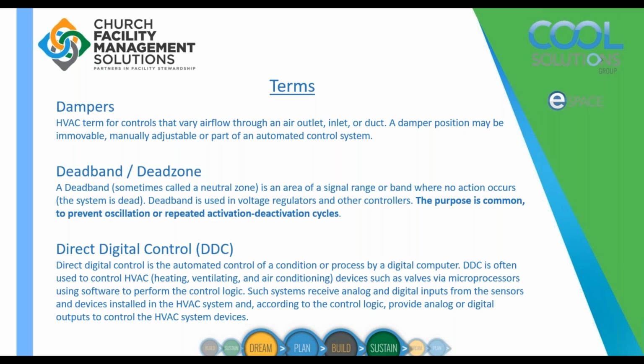Many thermostats have built-in deadbands that they'll modulate in between 2 to 4 degrees. So just understand, scheduling them close doesn't necessarily mean that you're going to keep that temperature constant. If you need to do that, so for example, in a server room, there's different ways and there's different controls that we would use to make sure that we have a constant temperature.